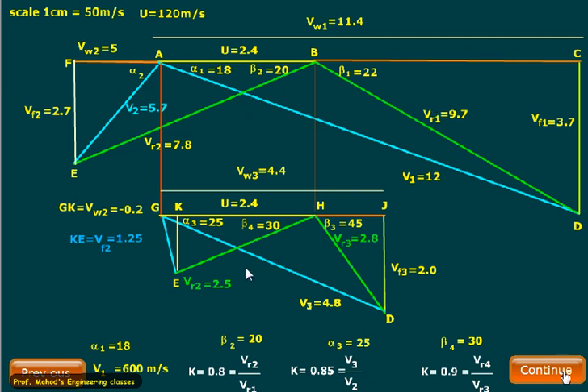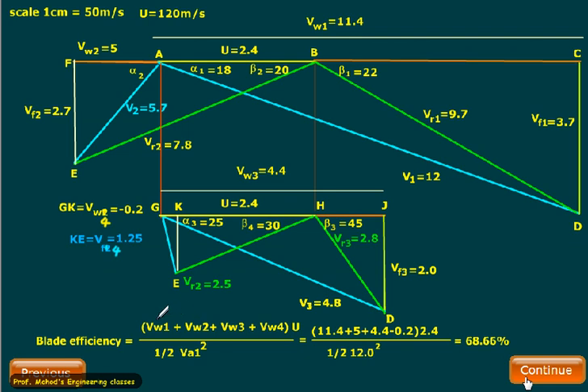In this fashion we can complete the first stage as well as second stage. This value is 11.4, and Vw4 you have to read as minus 0.2 centimeters, and Vf4 equals 1.25. To obtain the blade efficiency, we'll compute the addition of all velocity vectors. This velocity vector is rightward so positive, this is leftward so also positive, this one is rightward so positive, and this one is also rightward. This outlet is outward, so that is why it was taken as minus value, multiplied by U divided by half V1 squared. Substitute all these values: 11.4 is Vw1, Vw2 is 5, Vw3 is 4.4, and Vw4 since rightward is minus 0.2. U is 2.4 and half V1 squared, which is V1 squared is 12 squared. Your blade efficiency comes out to be 68.66%.